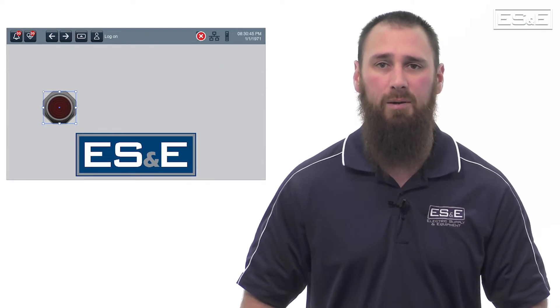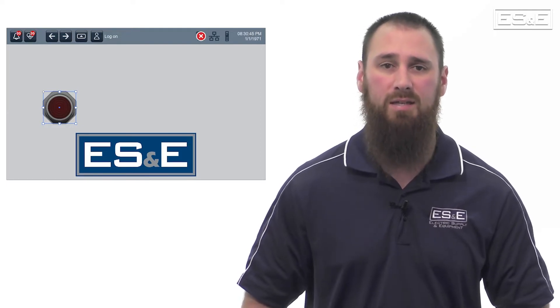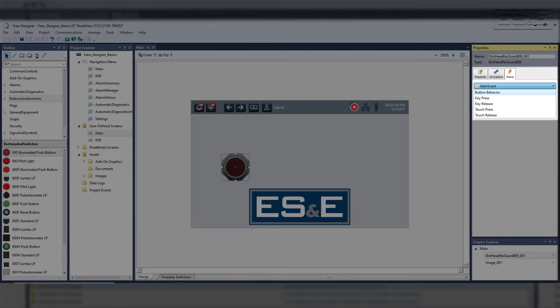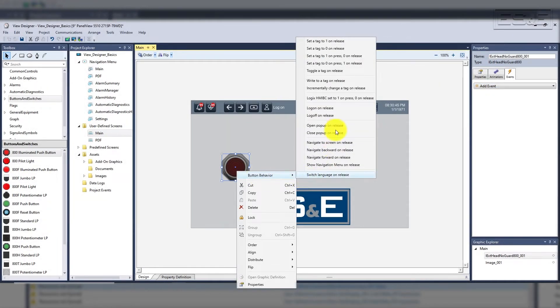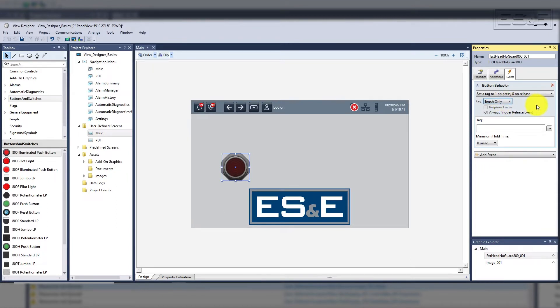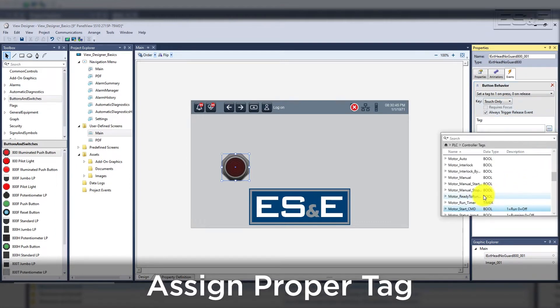The button is animated, but we need to make it do something, which requires adding an event. All buttons can be configured to be any style of button — momentary or maintained are examples. Events can be added on the events tab in the property window or by right-clicking on the object and selecting button behavior. For this button, we will use a momentary style event with one on press and zero on release. One unique feature present if you have a 5510 or 2715 is the ability to assign it to a key or leave it as touch only. By default it will always be touch only, and if you have a 5310 or 2713, this will not be an option. Then we will assign the tag Motor Manual Stop push button by selecting the ellipses and browsing the PLC tags.